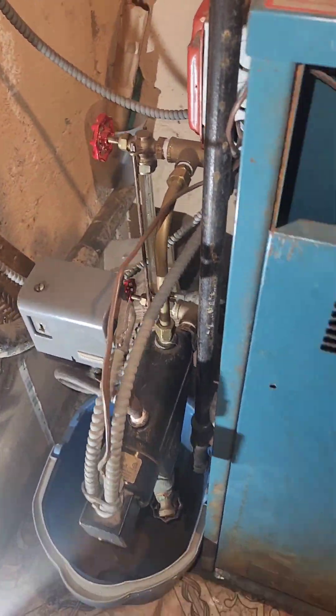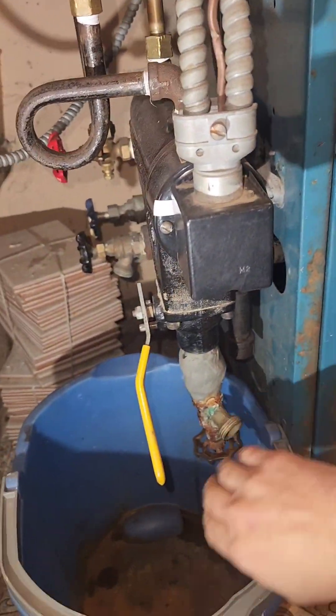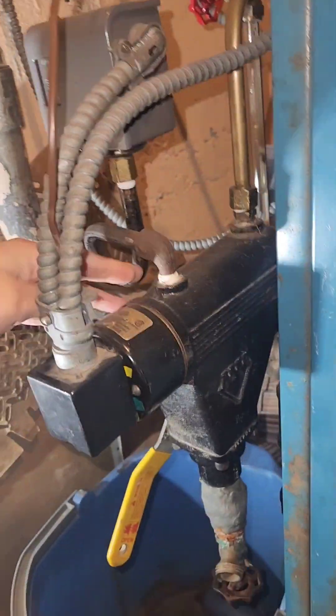Hey everyone, this is Paul from Day2DayFixes. Today we have this steam Burnham boiler — it's a little on the older side, so we're going to do a little bit of maintenance. First, we're going to turn off the power to the boiler, then we can drain the water from this low water cutoff.